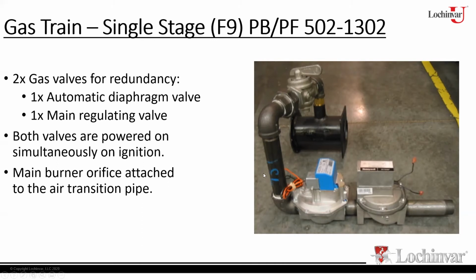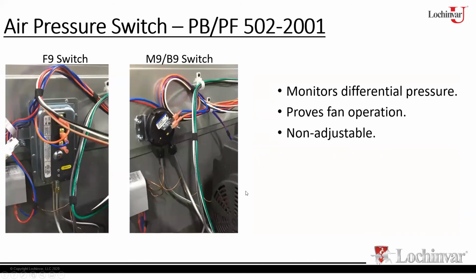So let's continue on. Let's talk about pressure switches. All right, here's the thing. With a negative regulation system, you really don't need a low air switch. I don't need to prove that the fan is running on a neg-reg system. The reason is because if the fan doesn't operate, remember, no negative suction from the fan. If it's not operating, no gas flows from the valve. All right, so it's a fail-safe. So I don't have to prove that the fan is operating.